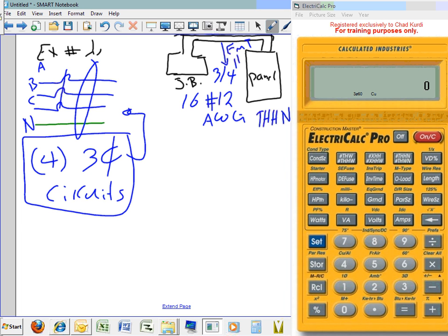If you put the 16 conductors, these are 4 circuits, 3-phase each with shared neutral. Common, we use it commercial all the time. So you're sharing a neutral. The voltage is 277 to neutral, or 120. It really doesn't matter what the voltage is, 120 or 277 to neutral.